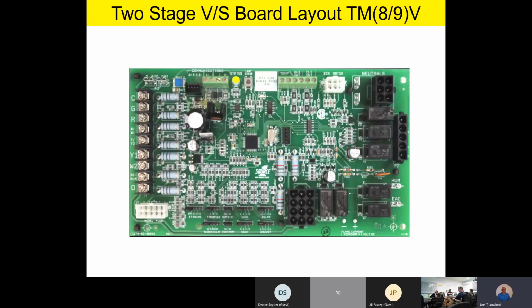So this morning, we take a look at our two-stage variable speed control board layout. Now remember, team, this is going to be on the TM8 or the TM9V furnace, and this is probably, I won't say the most complex, but it has the most features of any of our furnace control boards, in the fact that we're going to have some two-stage heating, two-stage cooling capability. And the neat thing about this board is that because the motor is a true variable speed, high efficiency motor, we're going to have some airflow adjustments on the board that we'll be talking about as well.